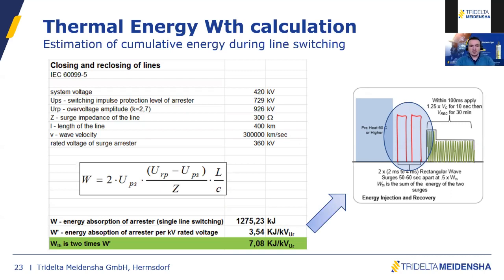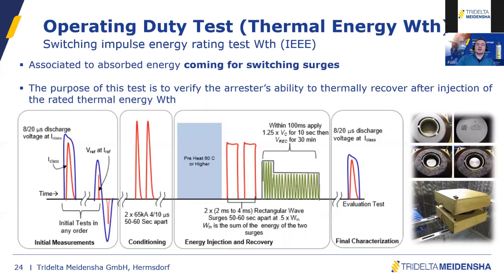So here is a typical example for a 420 kV system where you need 7 kilojoule per kV rated. It's important to see that this is per kV rated, and the reason I will show here. This will be the last part of my presentation, of my section.